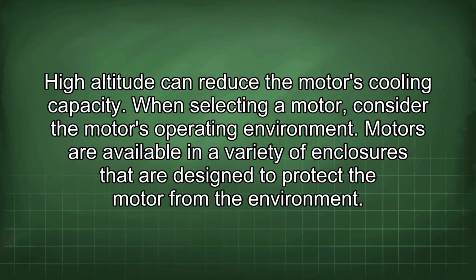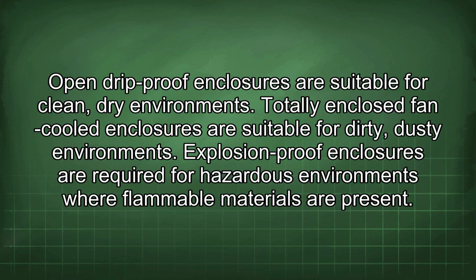Motors are available in a variety of enclosures that are designed to protect the motor from the environment. Open drip-proof enclosures are suitable for clean, dry environments. Totally enclosed fan-cooled enclosures are suitable for dirty, dusty environments. Explosion-proof enclosures are required for hazardous environments where flammable materials are present.